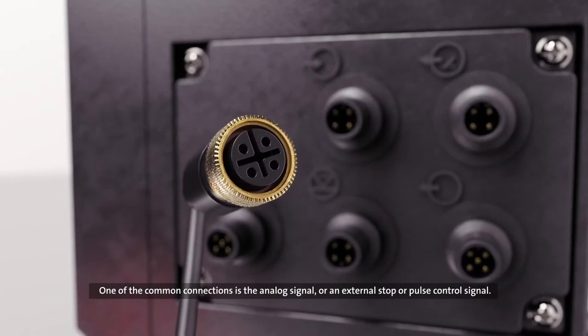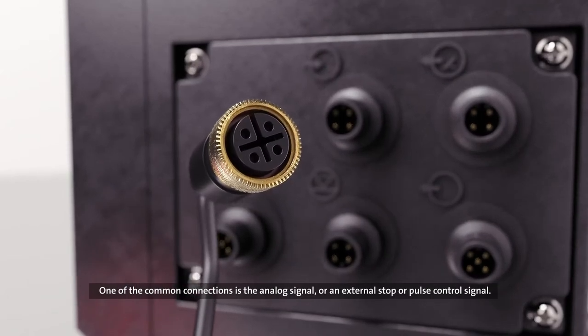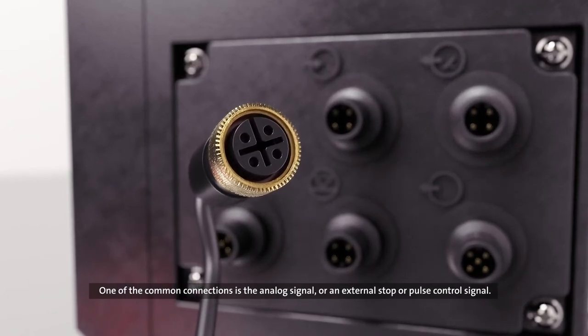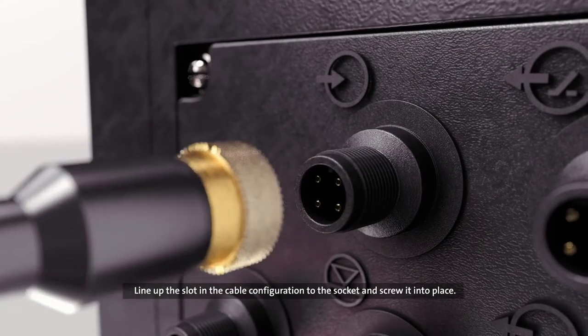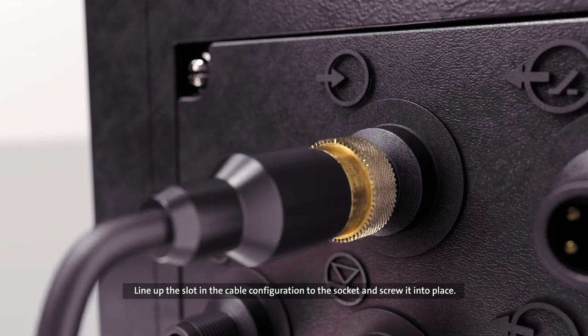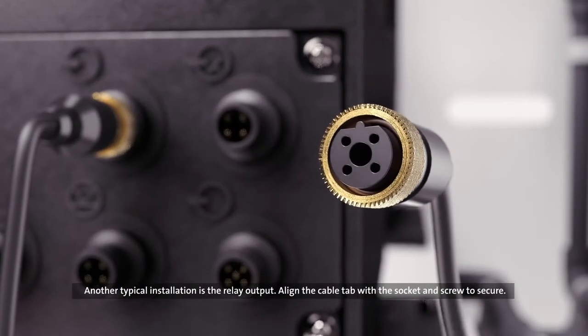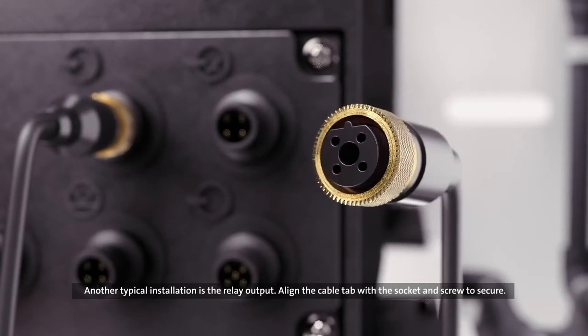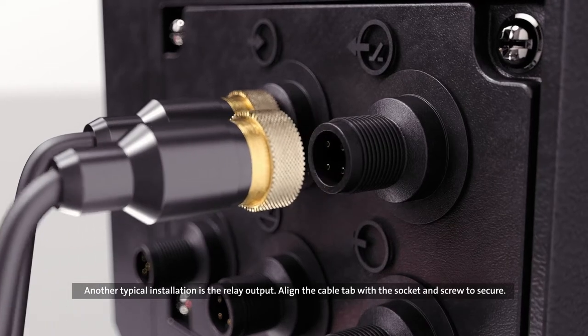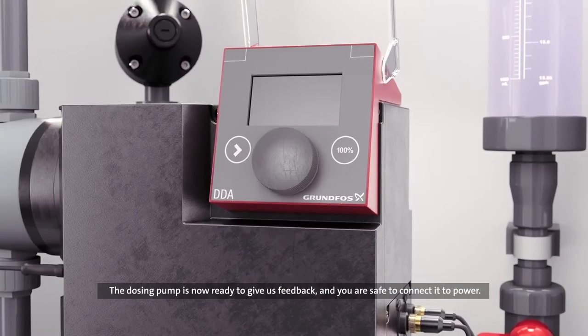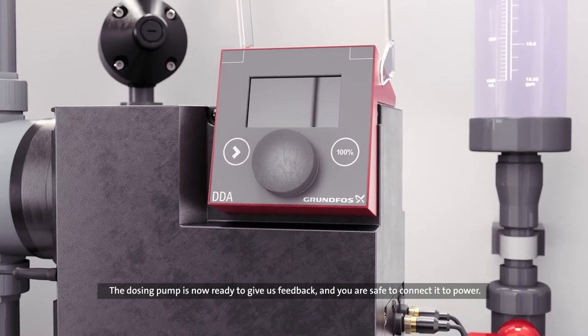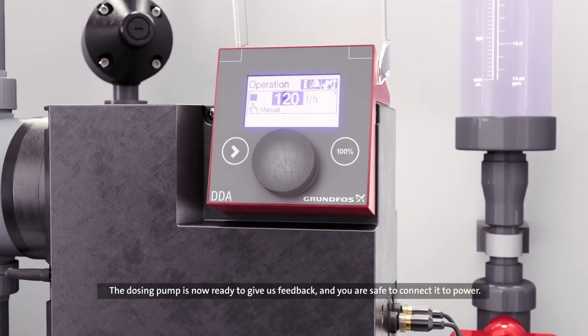One of the common connections is the analog signal or an external stop or pulse control signal. Line up the slot in the cable configuration to the socket and screw it into place. Another typical installation is the relay output. Align the cable tab with the socket and screw to secure. The dosing pump is now ready to receive input signals and give us feedback. And you are safe to connect it to power.